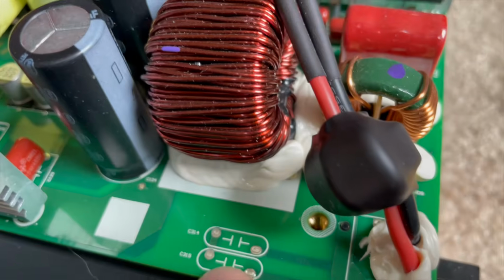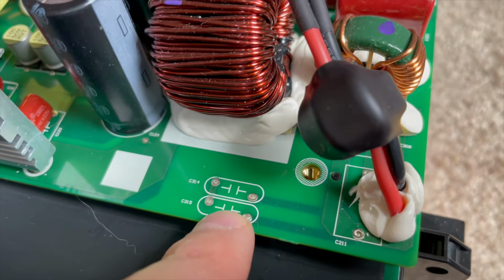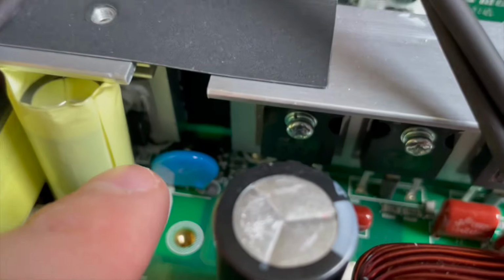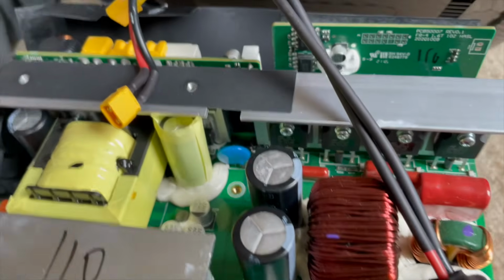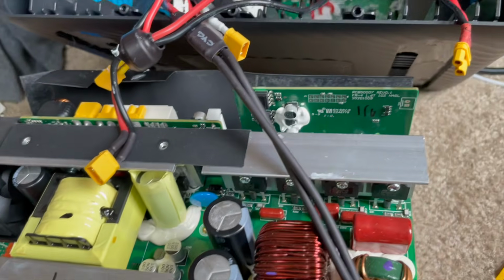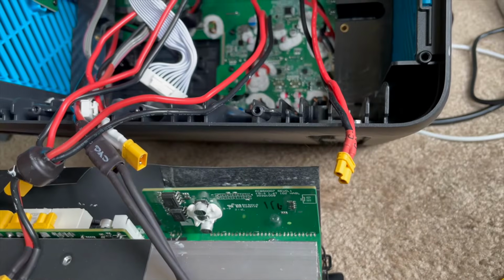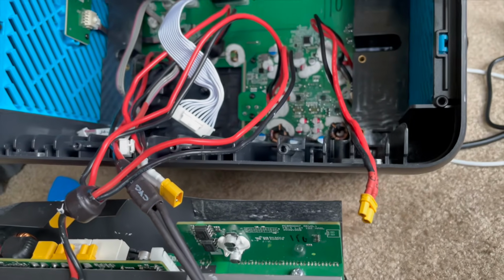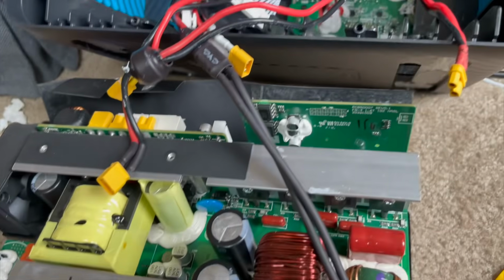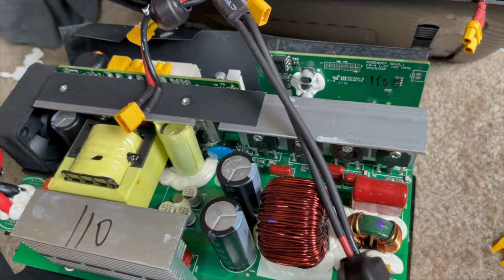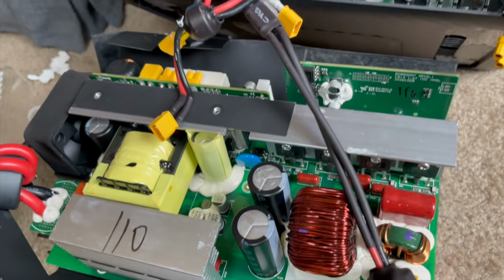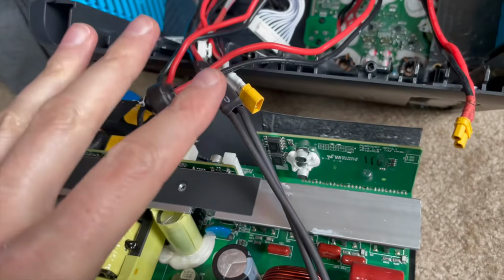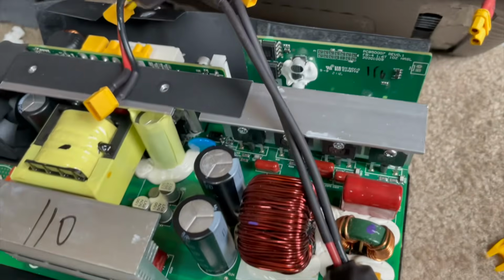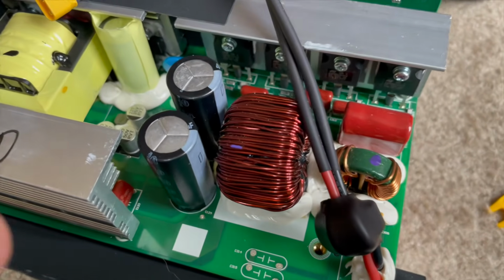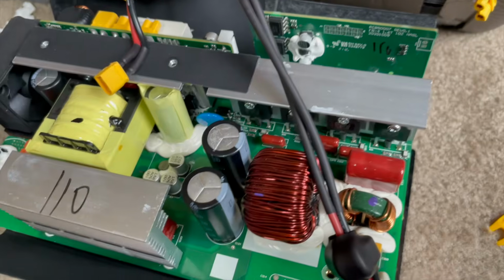Looks like they had some locations for more Y caps but decided not to fit those out. There is one here. There was a bunch on the PowerHouse II 400, which surprised me a little. If there was a grounding screw on this, when using it in battery mode to provide an AC output, and you wanted to ground the whole chassis, I could see where the Y caps would come into play, but I don't see why they would come into play without any external grounding, which this doesn't have.